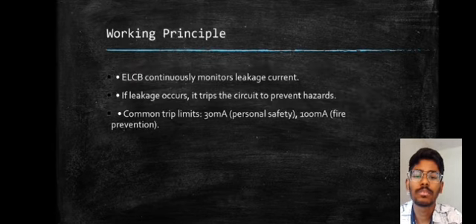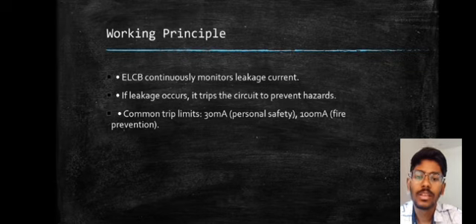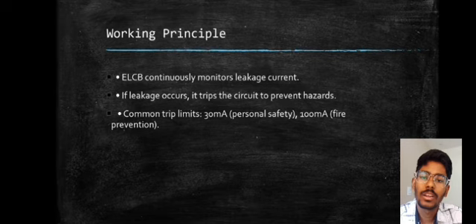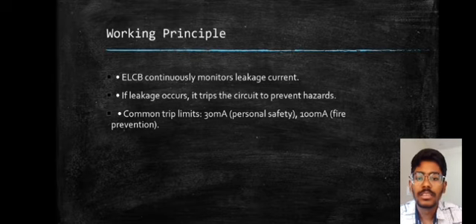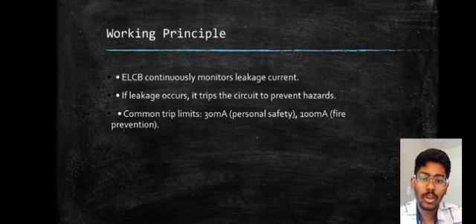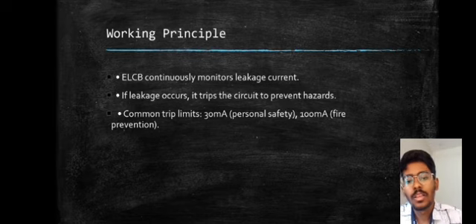The working principle of ELCB. ELCBs work by continuously monitoring the electrical current. Normally, the current in the live and neutral wires is equal. If leakage occurs, such as when a person touches a faulty wire, there is an imbalance. The ELCB detects this and trips the circuit, cutting off power and preventing harm.